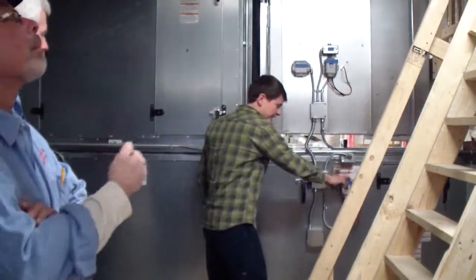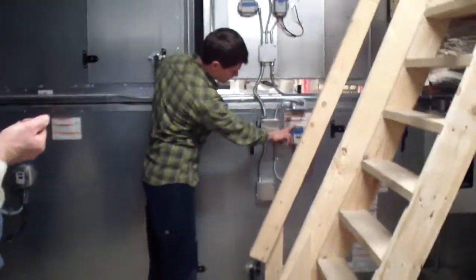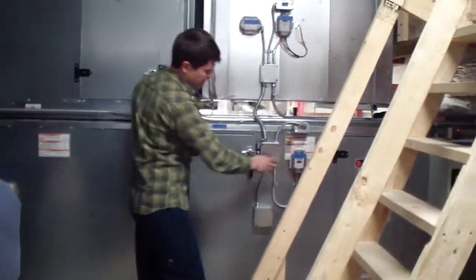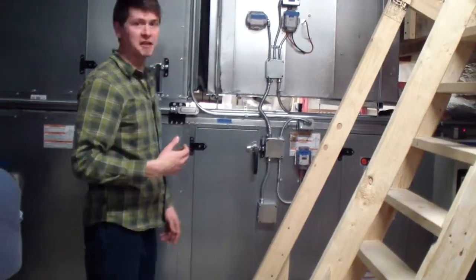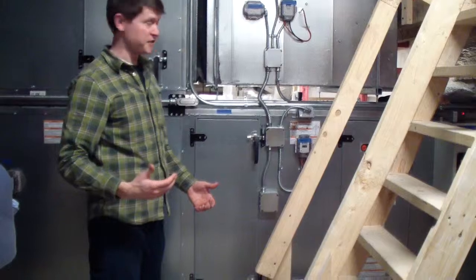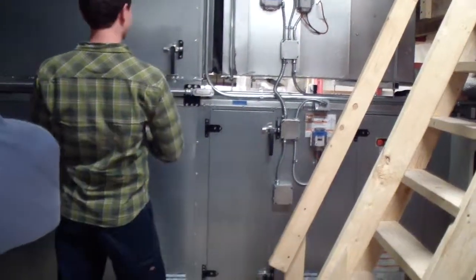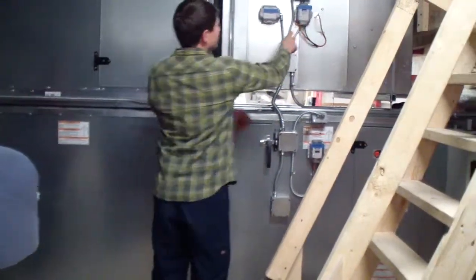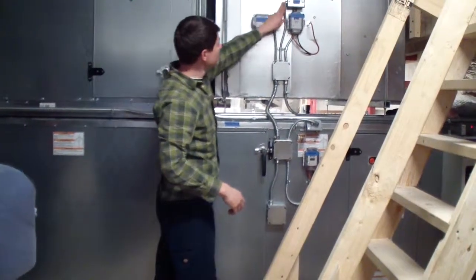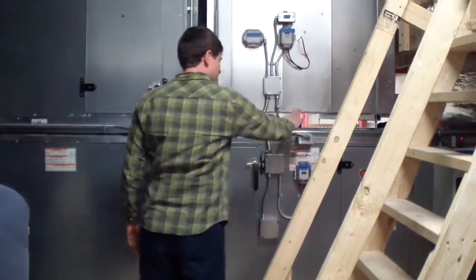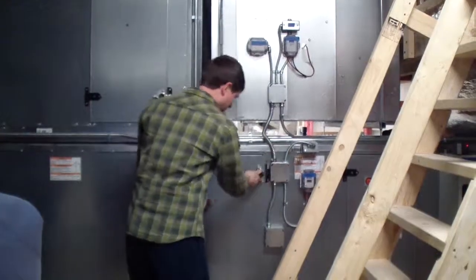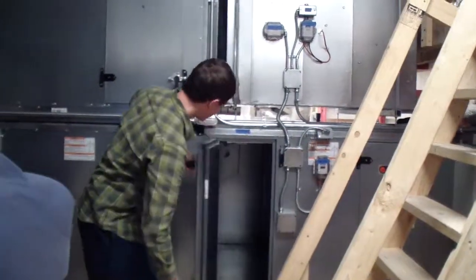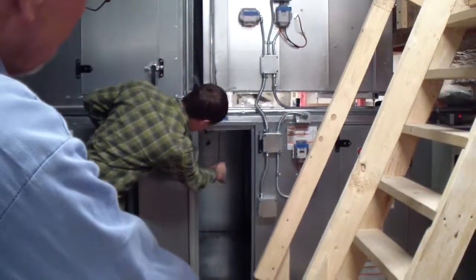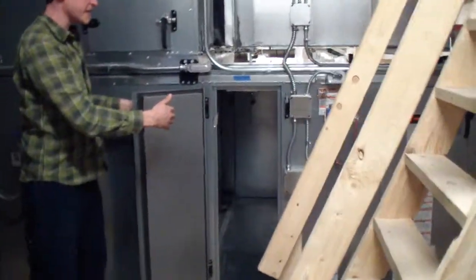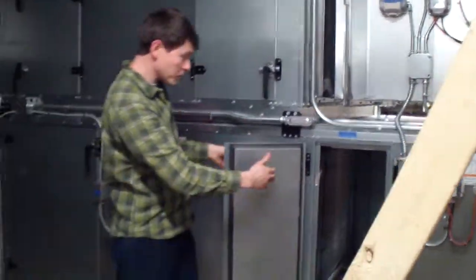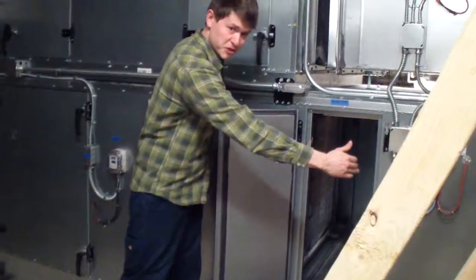Your supply fan CFM. So this is looking at velocity pressure, and then through a calculation we're changing it to what you're actually reading in your CFMs. And it's the same thing for the return fan. And you've got a return fan humidity, a return air temp. You've got your thermostat, which is wrapped around the coil, which you can see right here. So it's on the discharge side of your hot water coil. And I believe that this is your chill water coil.